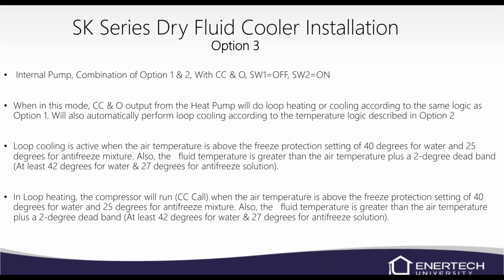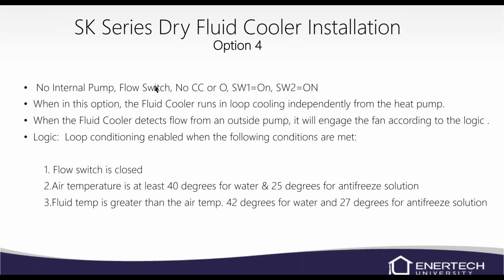In loop heating, the compressor will run when there's a CC call from your thermostat. When the air temperature is above the freeze protection setting, it's going to run. Also, the fluid temperature is greater than the air temperature plus your 2 degree deadband. So this option 3 is an internal pump, and it's a combination of options 1 and 2.